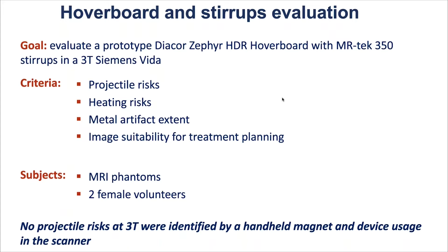As subjects for the test, we used MRI phantoms and 2 female volunteers. Our initial tests with a handheld magnet showed that there were no projectile risks at 3 Tesla, and it was possible to use the hoverboard and stirrups in such a scanner. For the heating and artifact tests, we have used 3 phantom setups. In test A, we used a large sphere at the edge of the mat on the hoverboard in a position that was simulating the pelvis. In tests B and C, we used phantoms very close to the stirrups so that we can quantify the extent of possible metal artifacts.